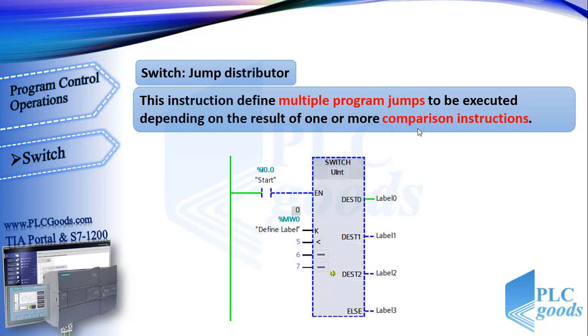Let's see the next instruction: switch, or jump distributor. This instruction defines multiple program jumps to be executed depending on the result of one or more comparison instructions. We can select the data type of the instruction. This instruction is like jump list — first we need to activate it, then the destination network will be determined based on some comparison. Here we can select comparators. For each condition, we must determine a label at the output part. If none of the conditions are true, the program will jump to the last destination.